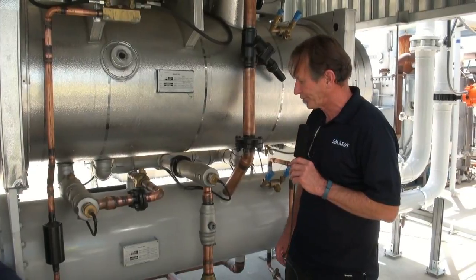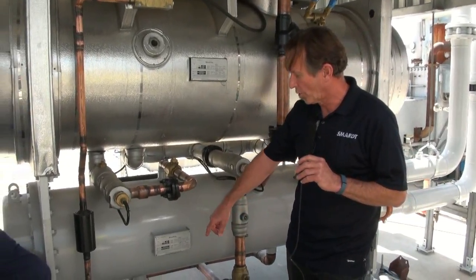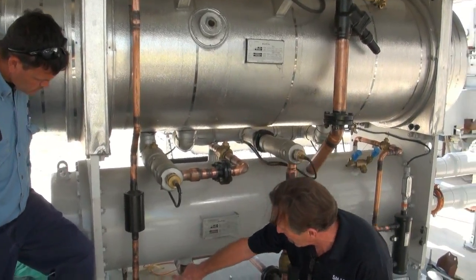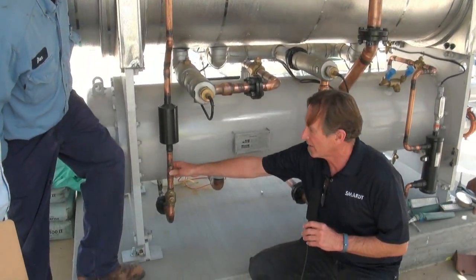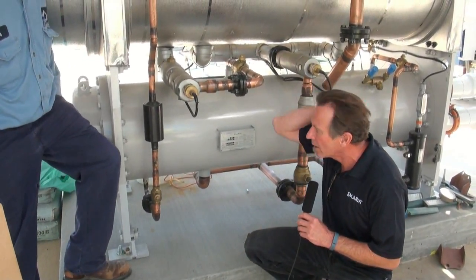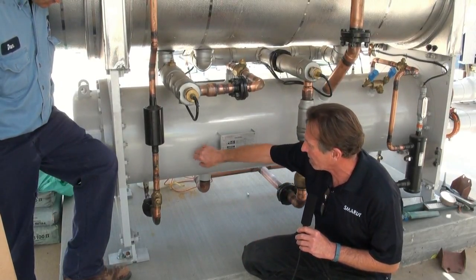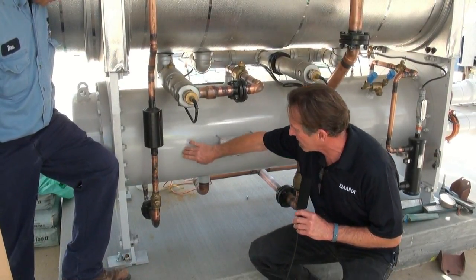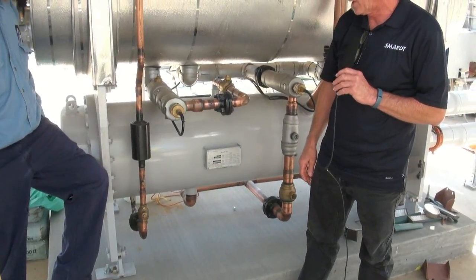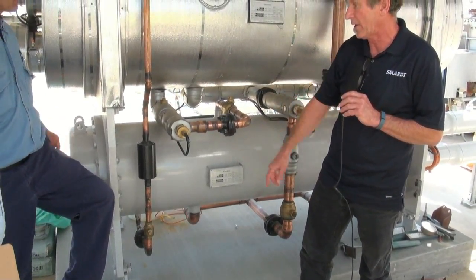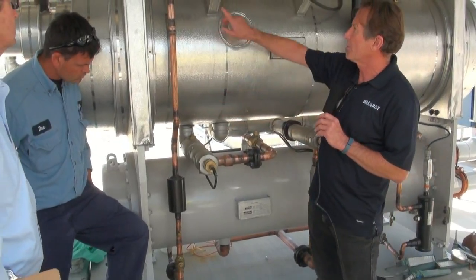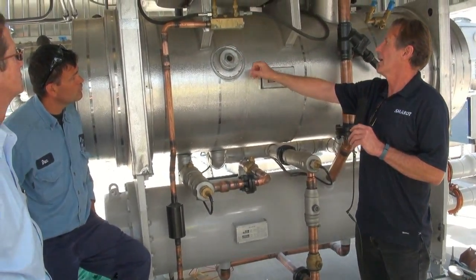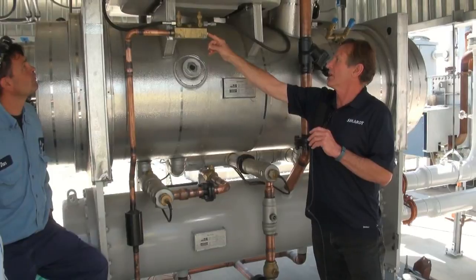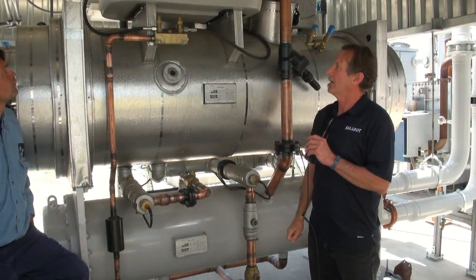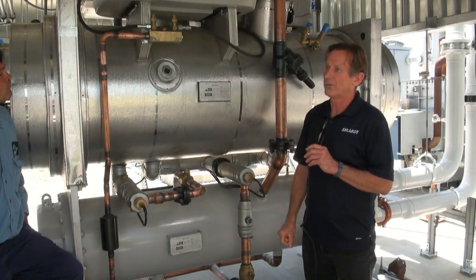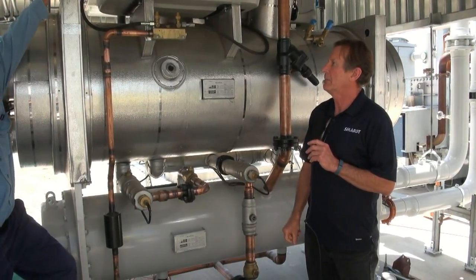We've got our motor cooling circuit here. It comes off the bottom of our condenser, so it gets liquid. We want a solid column of liquid at all times in this line, so it gets liquid right off the bottom of the condenser. So if there's any liquid in this condenser, it's going to be fed into this line. It comes up to a manifold, which, you probably can't see it on the video, but you've got a sight glass here on the side, and you want to see that full, typically all the time.